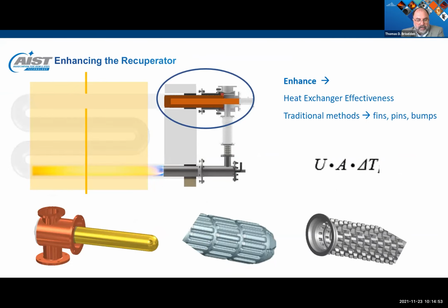So how do we enhance the recuperator? The effectiveness of the heat exchanger recuperator is driven by the overall heat transfer coefficient and surface area. The temperature tends to be fixed by the application. Recuperators are designed as simple straight tubes or enhanced with fins and bumps. With this type of design, in a parallel flow heat exchange design, overall system efficiencies are typically 60 to as much as 68%. Enhancing this design needs to address both improvements to the surface area and heat transfer coefficient in order to minimize pressure drop in the system.